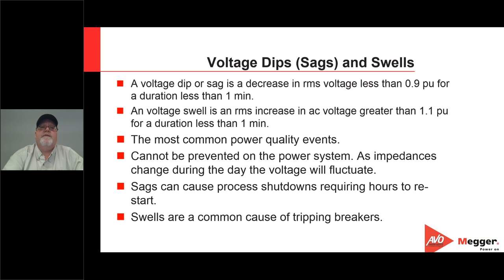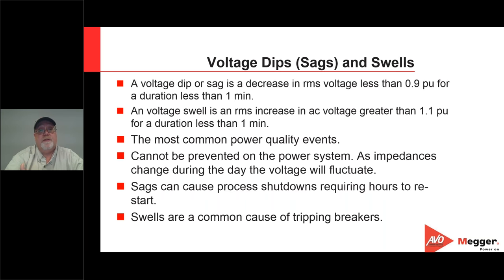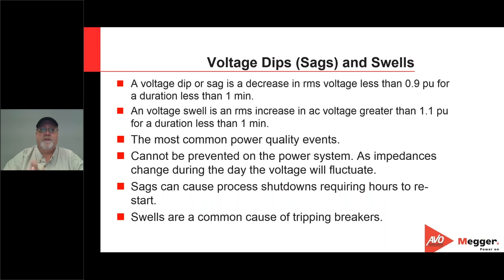We also have voltage dips, SAGs, and swells. You may hear the terms dip and SAG used interchangeably — in the United States we use the term SAG to represent a decrease in RMS voltage less than 0.9 per-unit, but for a duration of less than one minute. Outside the United States the term dip is typically used. Whenever you see dips or SAGs, they're talking about the exact same thing — it's just where you are in the world.